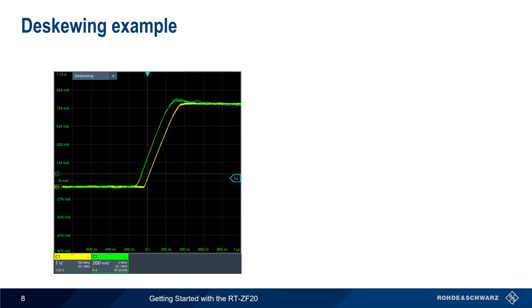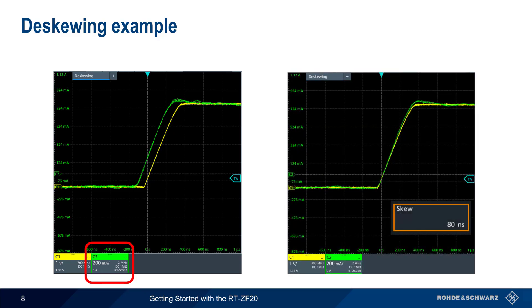Let's look at an example of alignment or de-skew adjustment. We've attached a voltage probe and current probe to the ZF20 de-skew fixture, adjusted the vertical and horizontal scaling appropriately, and we're triggering on the rising edge of the voltage waveform. Here we see that the voltage waveform, in yellow, and the current waveform, in green, do not overlap. We then go into the current probe menu and adjust the amount of skew — in this case by 80 nanoseconds — until the two waveforms overlap.